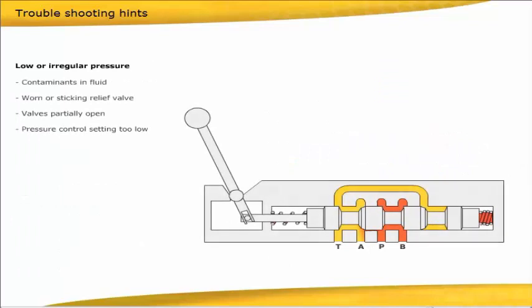Worn bearings. Low or irregular pressure. Contaminants in fluid. Worn or sticking relief valve. Valves partially open. Pressure control setting too low.